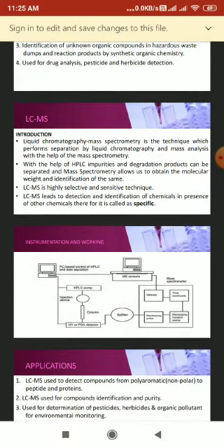Instrumentation and working of LCMS. The LCMS instrument can be interfaced by electrospray, particle beam, thermospray. Electrospray is the most widely used interface. The spray needle is used as a bridge to connect the liquid chromatography with the mass spectrometer, but the separate emitter is flexible as well as convenient.